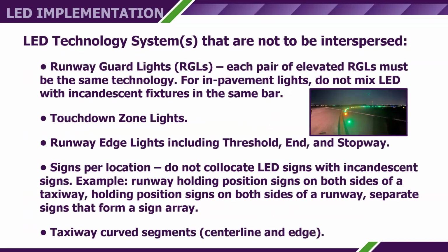And it tells us which LED technology systems are not to be interspersed. First one it gives us is guard lights. Each pair of elevated runway guard lights must be the same technology. For in-pavement lights, do not mix LED with incandescent fixtures in the same bar. So basically you could change out your incandescents, make them LEDs one bar at a time, so that they're uniform across that intersection. Touchdown zone lights, it's either all LED or all incandescent. Runway edge lights, including threshold, end, and stopway, all LED or all incandescent.